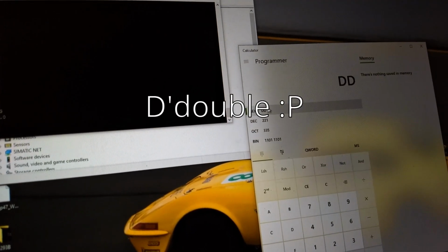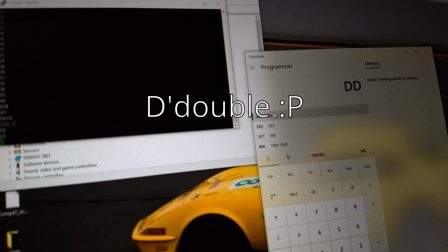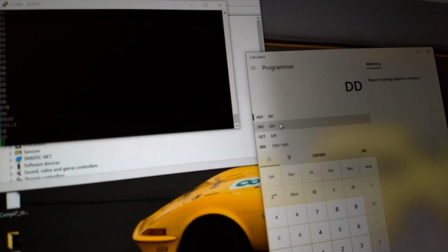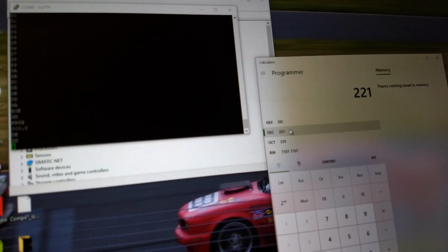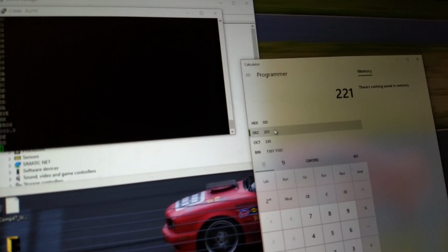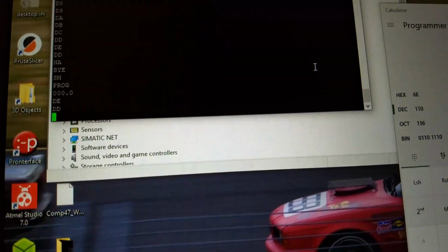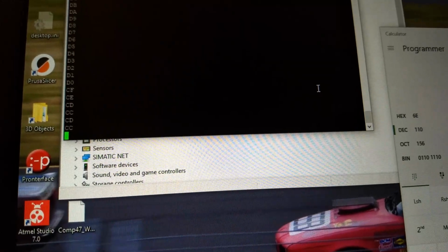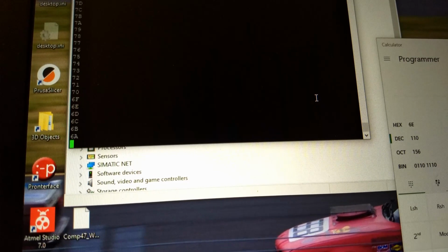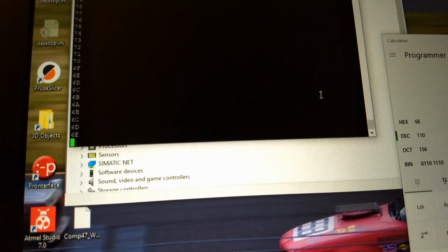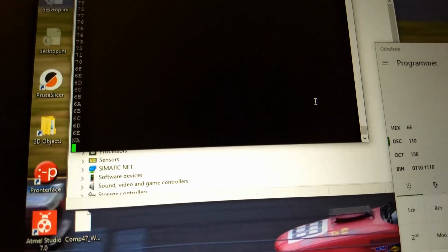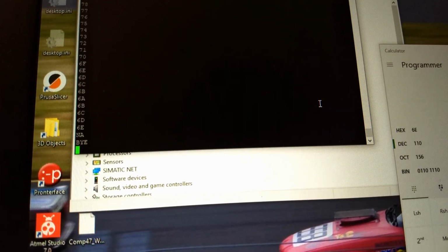So if we wanted to double the power output of this, which I'll just do for demonstration's sake, we want to divide that by half. So it's only reading half of the actual value. So take that, divide it by two, and we can see the hex result is 6E. So if we come here, hold minus, yeah, you use the minus and plus keys to modify these values. So you hold minus, get all the way down to 6E, come back up a bit, and you can go ahead and hit enter, and then hit shift R, which will lock it out.